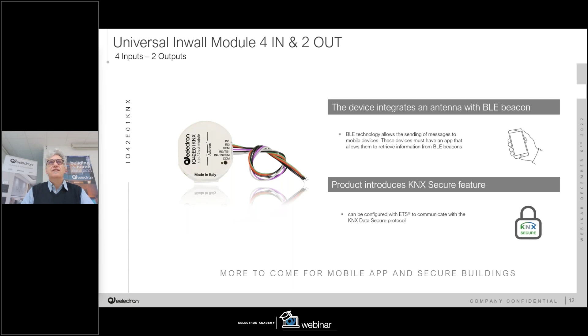Most devices in our price list today have a heartbeat function, capable of creating a telegram on the bus to signal that they are alive. For older devices, or to avoid increasing bus traffic on the trunk, you can use this kind of device instead, capable of monitoring the status of other KNX devices on the same trunk. The idea is to report this information to an upper level, a BMS or visualization software, to create warnings for the building manager and prevent issues with components not working properly.